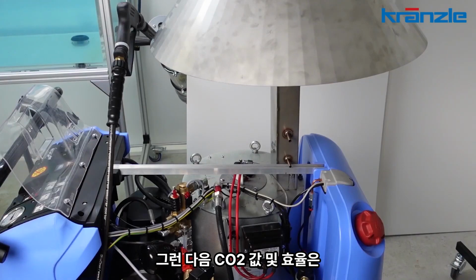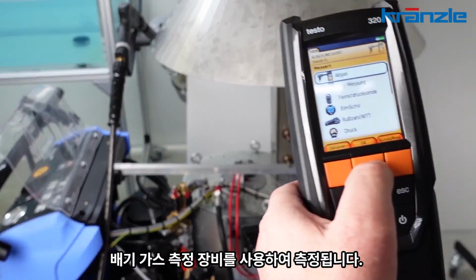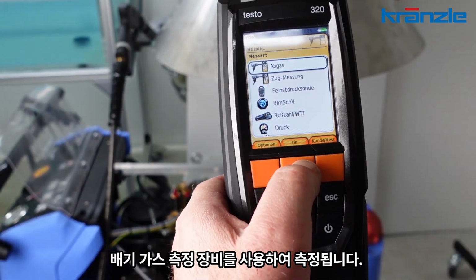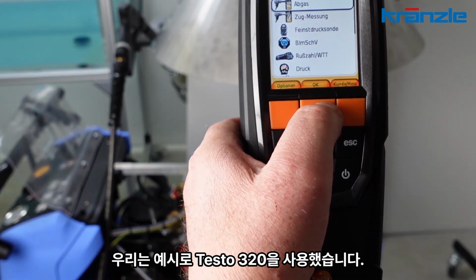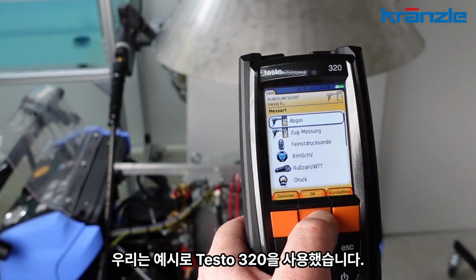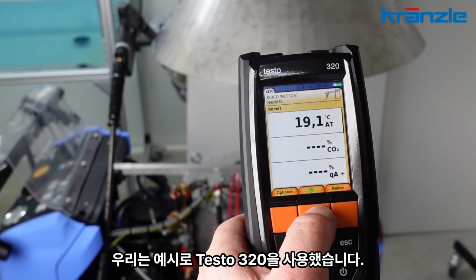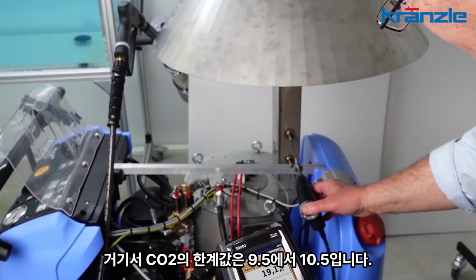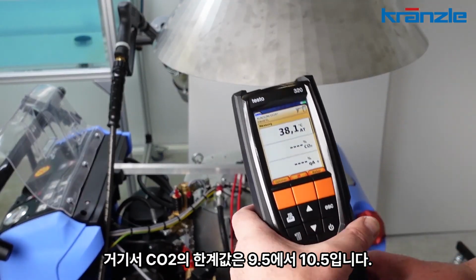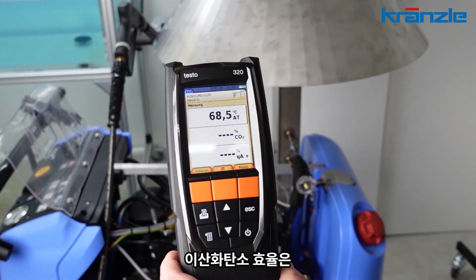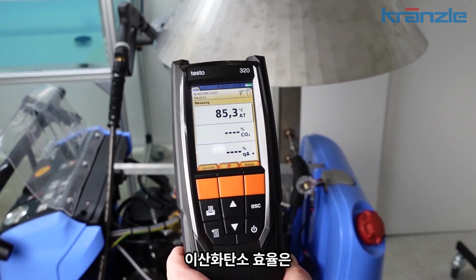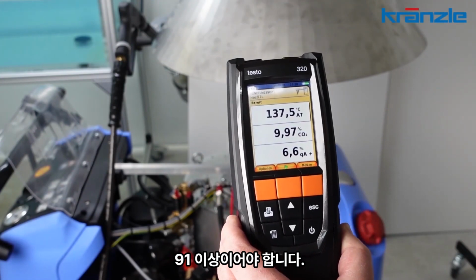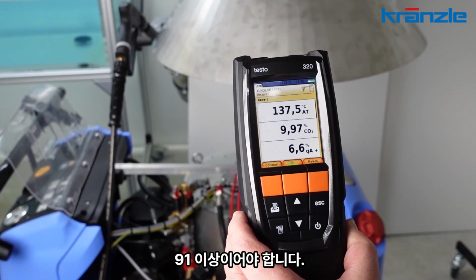Then, the CO2 value and the efficiency are determined with an exhaust gas measuring device, which we have done with a Testo 320 in our example. There, the limit value of CO2 is 9.5 to 10.5 percent carbon dioxide. The efficiency has to be 91% or higher.